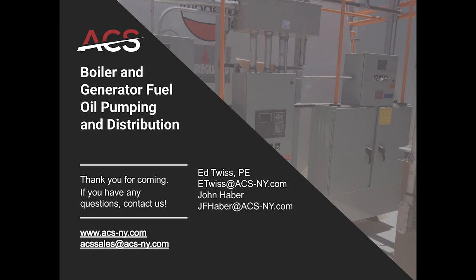There's another option nowadays also for New York City, which is the flexible pipe that's been out on the market, and that would only require a 2-hour fire rated riser shaft as opposed to 4-inch masonry. But it's not just flexible pipe, it's double wall flexible pipe with a continuous detection system in it. That's correct. So that has to meet all those requirements in order to use that. And that is something that is approved for use in New York City.